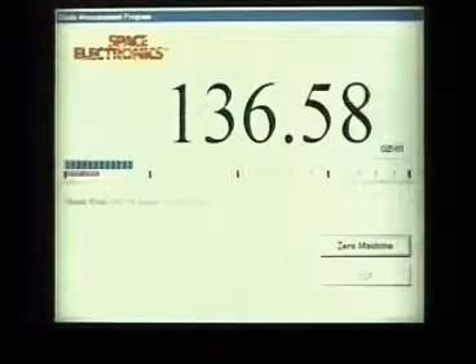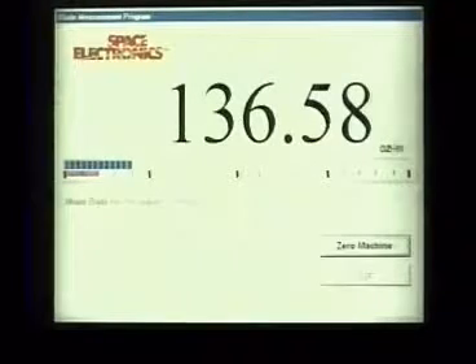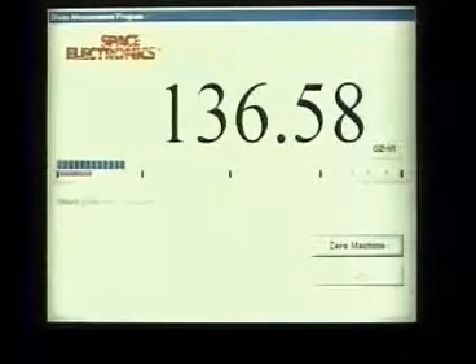In order to illustrate the variation in moment weight reading, I'm going to change the resolution of the readout so that it reads to the nearest thousandth of an ounce inch. First I select the setup menu in order to change the configuration. I go into the units mode and I have to type in a password. This password is required so that a machine operator won't inadvertently change some of the critical parameters of the measurement. And then I can scroll down until I get to the number of digits beyond the decimal point, and I'm going to change that from 2 to 3. And then accept that change.